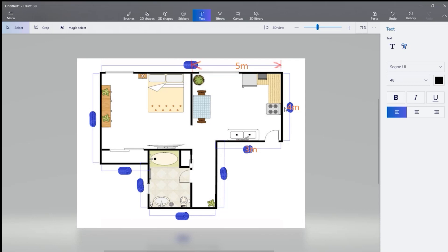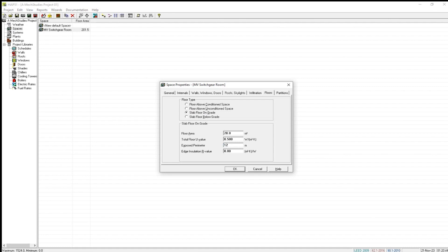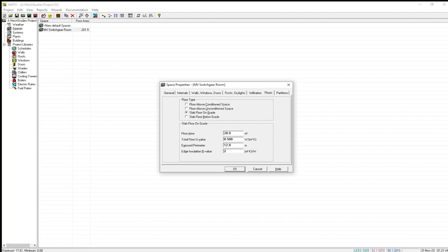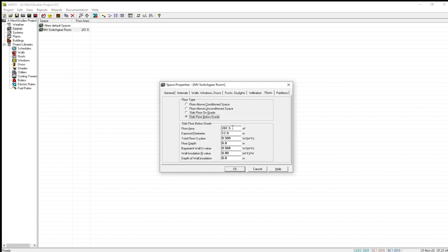The exposed perimeter is 5 meters plus 4 meters plus 3 meters, which equals 12 meters. So we write 12 meters here. The edge insulation R-value — we have seen this is the edge insulation — let us consider that the R-value is 2 m²·K/W. We write 2 here, and we have completed the slab floor on grade inputs.